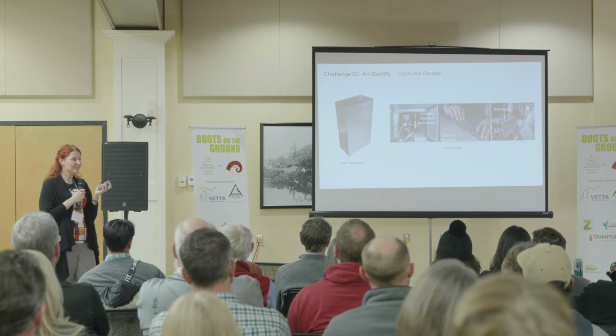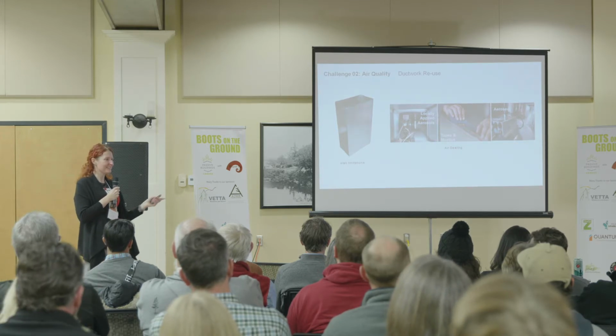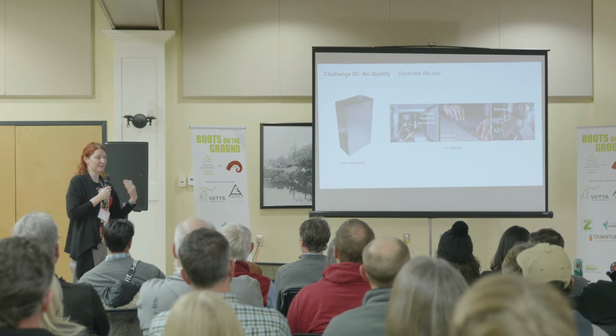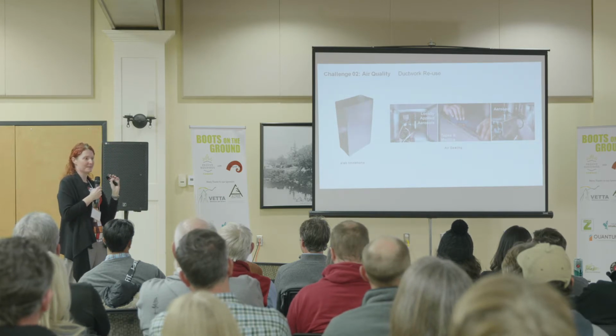We can use locally applied aerosols, so there are actually little robots that run around inside the ductwork and apply a spray-applied mastic on the inside. We can also do a traditional taping process, but it would require removing all of the fire barriers around these exhaust ducts, so it's going to be quite intensive.